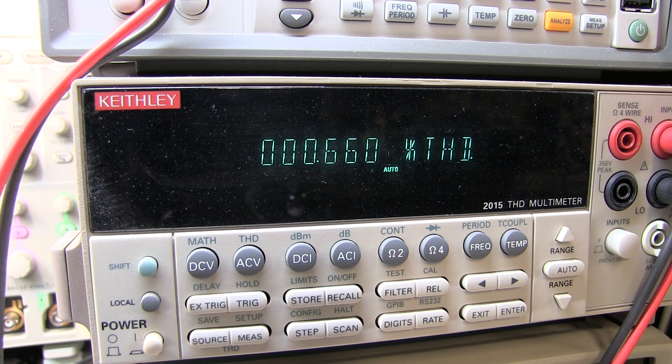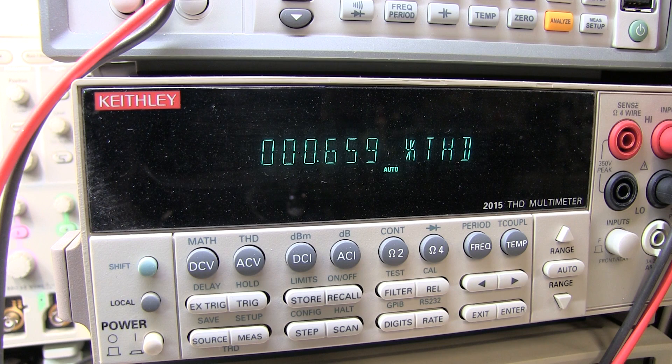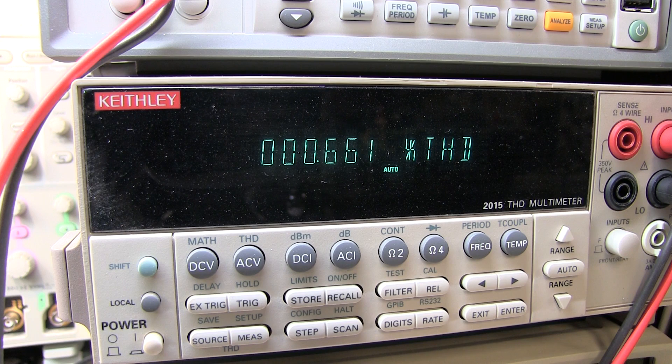Now that's reading about 0.66%. So we went from about 1.6% down to 0.6% THD according to the multimeter here.